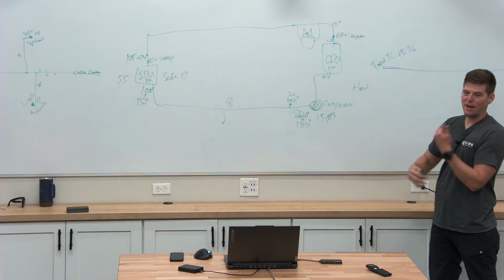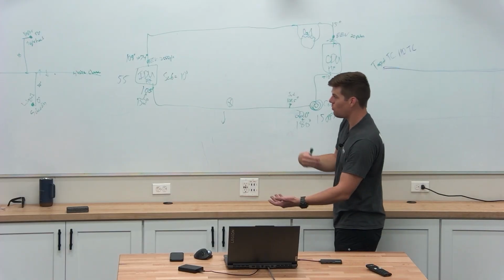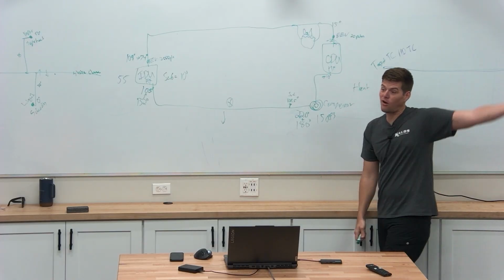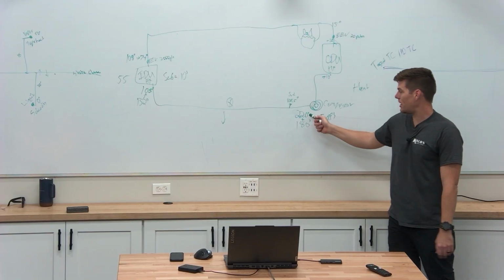What do we need to get oil back? We need flow. We need refrigerant volume and velocity. We're not getting either one right now. We have a ton of volume, but it's not going anywhere. So my discharge temperature goes from 180 to 220.